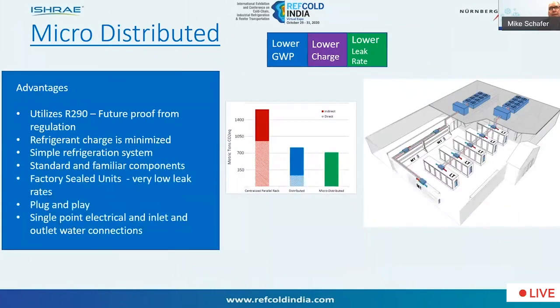So what are the advantages? Well, obviously R290, using a natural refrigerant, is future-proof from regulation. We've got the refrigerant charge reduced, minimized to probably the lowest level it can be, probably 90% reduced compared to a standard DX system. The other advantage we talked about is that it's a very simplified refrigeration system, a DX system, very understandable. All the components are standard HFC type components, obviously rated for propane.